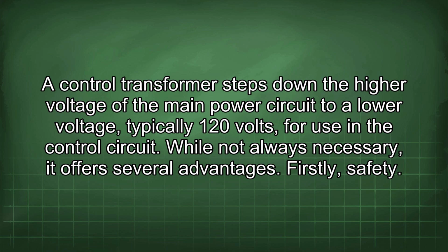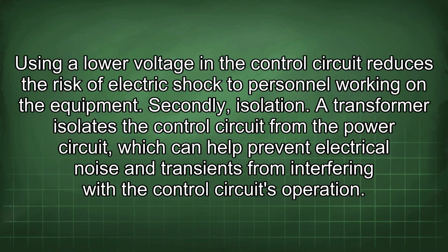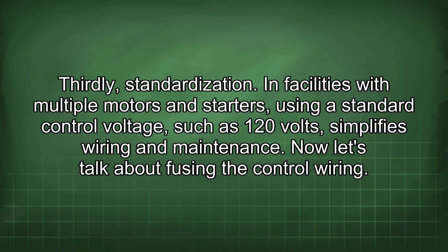While not always necessary, it offers several advantages. Firstly, safety. Using a lower voltage in the control circuit reduces the risk of electric shock to personnel working on the equipment. Secondly, isolation. A transformer isolates the control circuit from the power circuit, which can help prevent electrical noise and transients from interfering with the control circuit's operation. Thirdly, standardization. In facilities with multiple motors and starters, using a standard control voltage, such as 120 volts, simplifies wiring and maintenance. Now let's talk about fusing the control wiring.